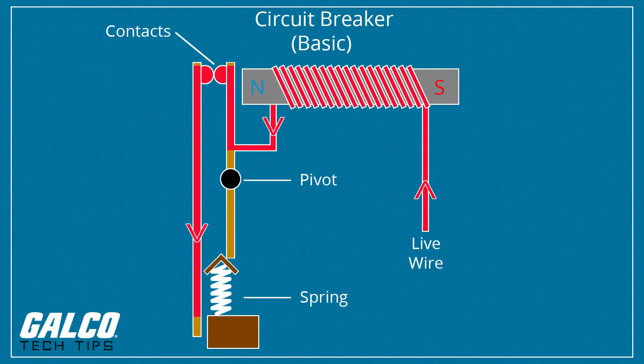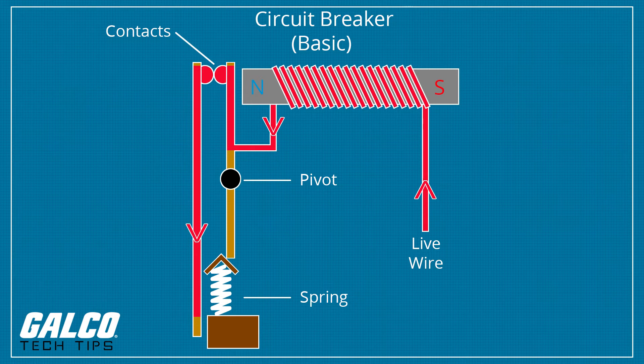A basic circuit breaker consists of a simple switch connected to either a bimetallic strip or an electromagnet. The hot wire in the circuit connects to the two ends of the switch. When the switch is flipped to the on position, electricity can flow from the bottom terminal through the electromagnet, up to the moving contact, across to the stationary contact, and out to the upper terminal.